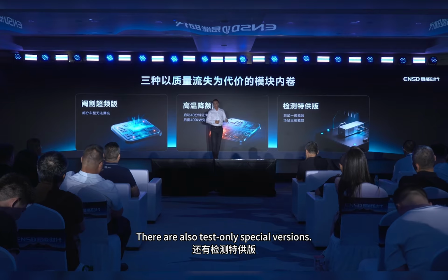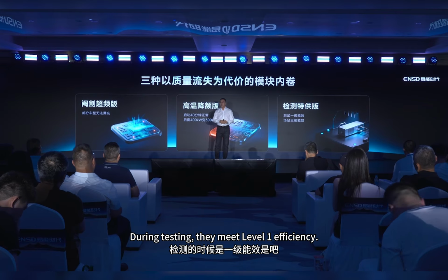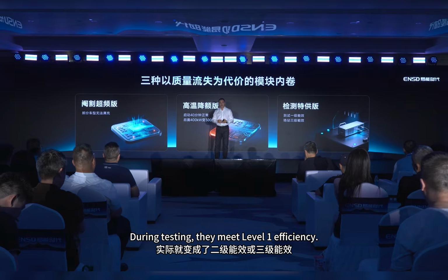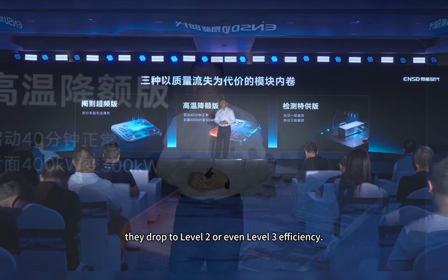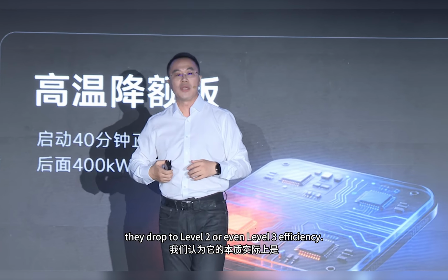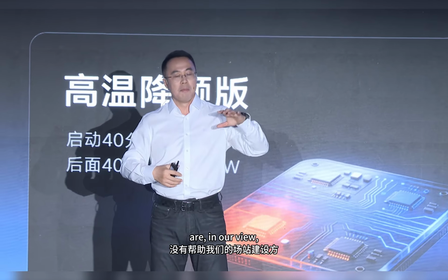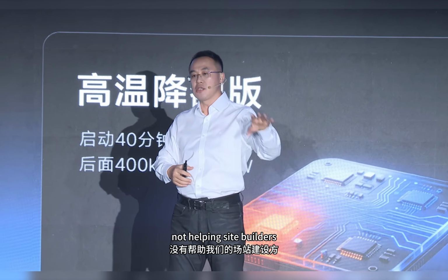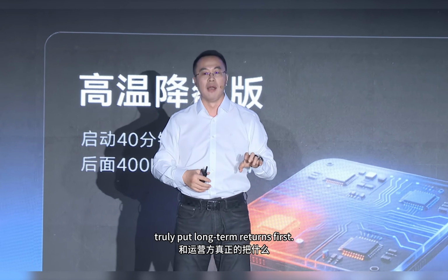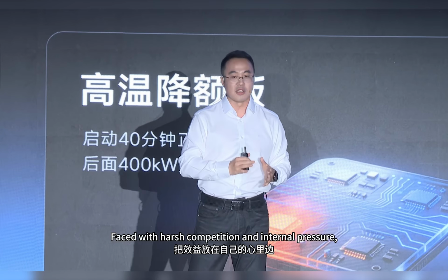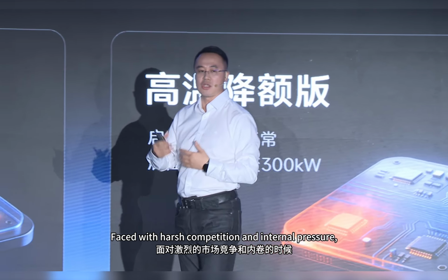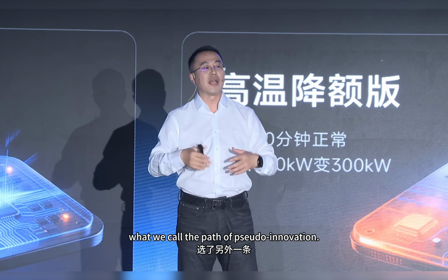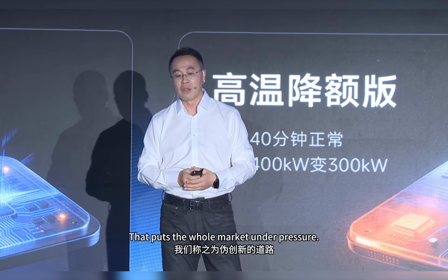There are also test-only special versions. During testing, they meet level 1 efficiency, but once they run at an actual site, they drop to level 2 or even level 3 efficiency. All of these are, in our view, not helping site builders or operators truly put long-term returns first. Faced with harsh competition and internal pressure, some people chose what we call the path of pseudo-innovation, which puts the whole market under pressure.